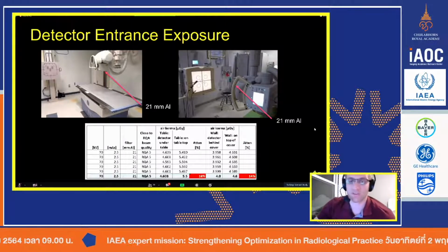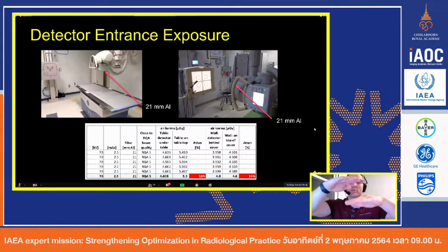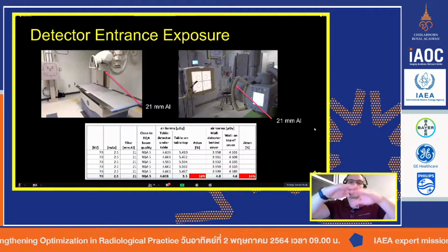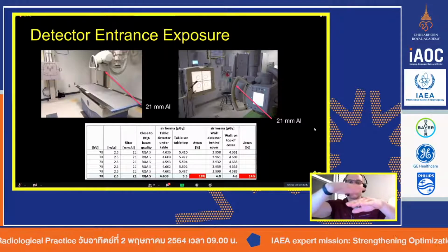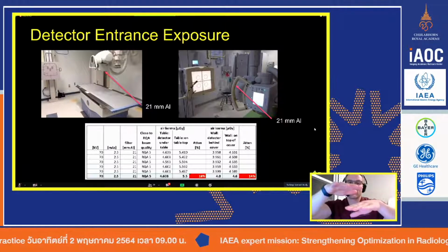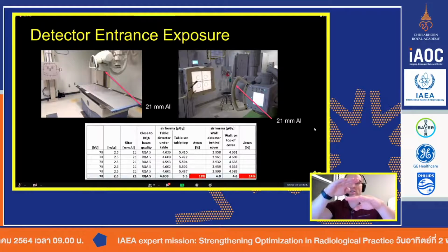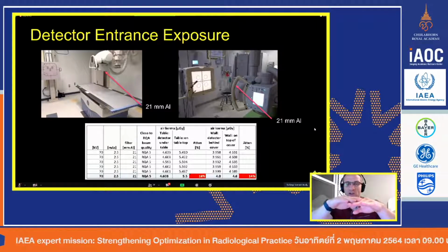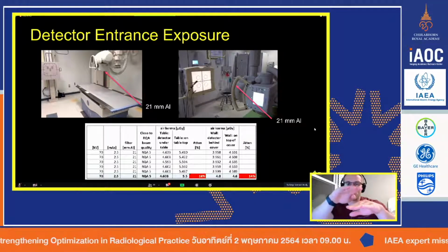Now, the last thing, of course, now that I know my attenuation, I need to know the distance. So there's going to be probably 5 to 10 centimeters, maybe somewhere in that range, maybe 8 centimeters, but there's going to be a specific distance from the top of the table to the detector itself, or surface itself. And so you obviously have to do an inverse correction to scale, because you're making a measurement 10 centimeters up. You have to calculate for how much it would change if your detector was actually 10 centimeters lower.